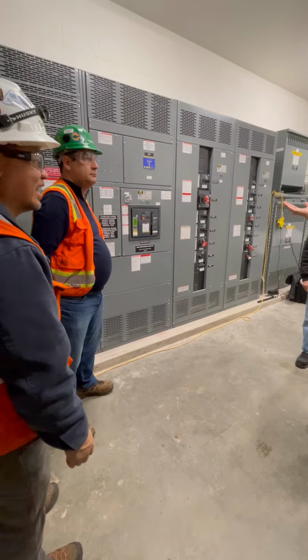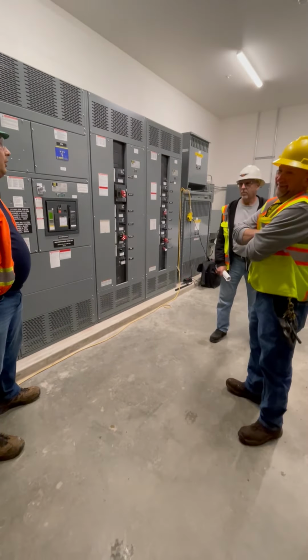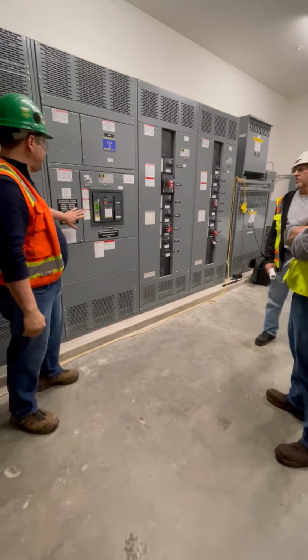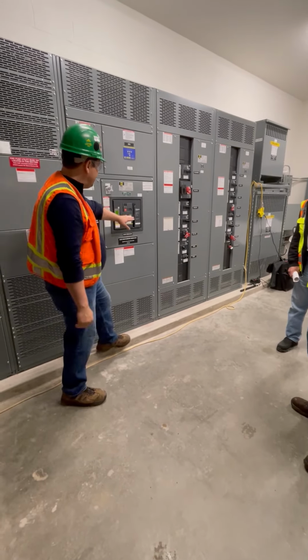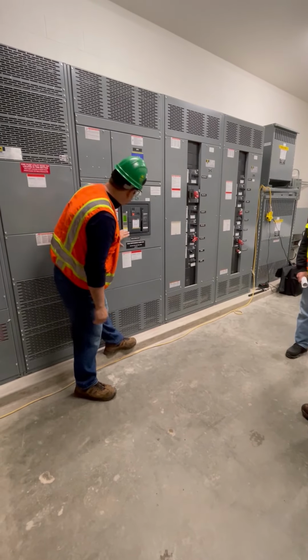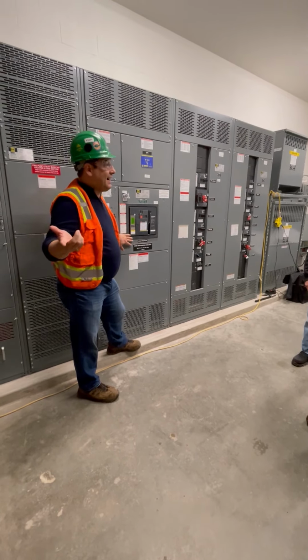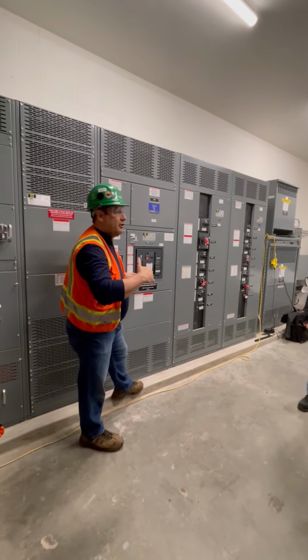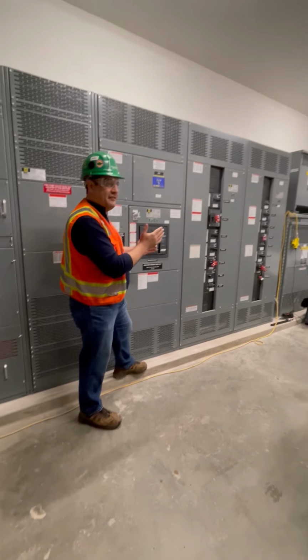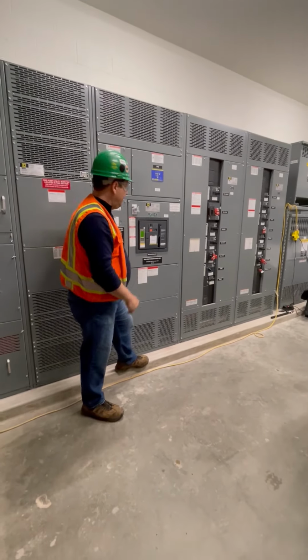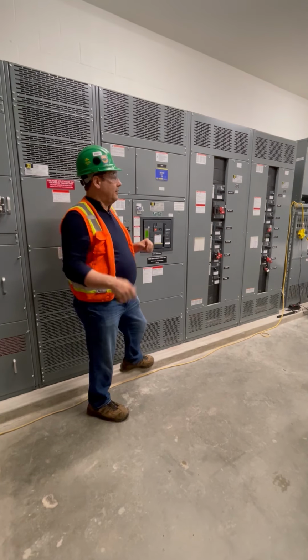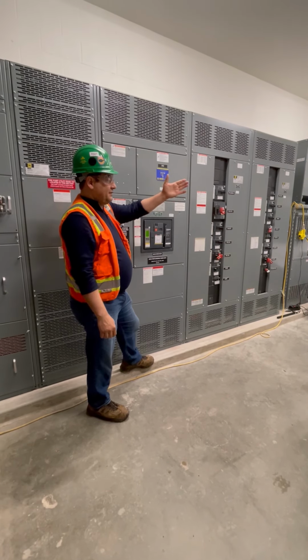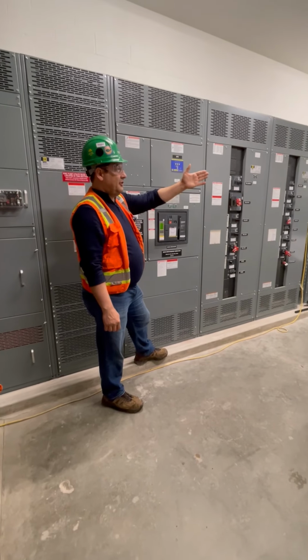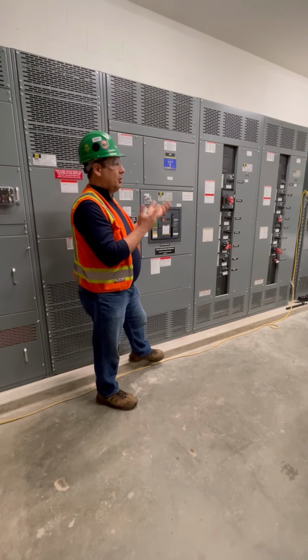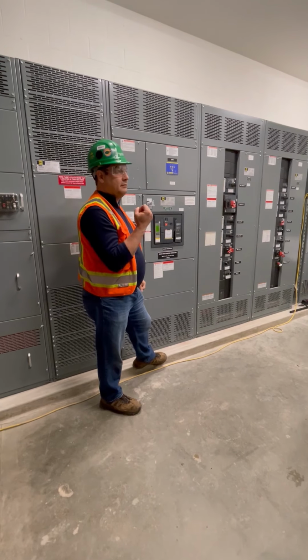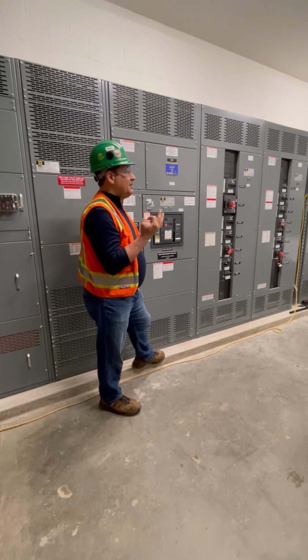So if we got half the school without power, we probably know it's right here. Here's what I suggest. These are set, the 3,000 amp, probably somewhere depending on what the setting is. 1,200 is the highest, but you can go down to 300, 400 on a ground fault. So it depends on where it's set. 400 amps, 500 amps, that's when it trips off, right? It could go up to 1,200, like you said. Now, the breakers downstream, let's say you have 40 amp, 50 amp thermomagnetic breakers downstream, they have a very long timing. Sometimes they can count for like 10 seconds before it trips.